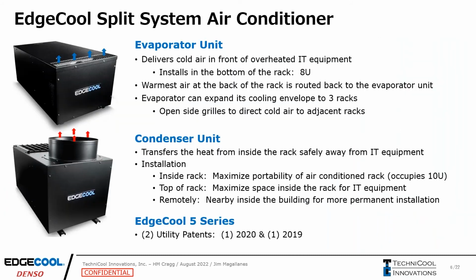So to go into a little bit more detail about our system, the evaporator, we're delivering cold air with the evaporator unit. It's always located at the bottom of the rack, and it occupies 8 U of rack space. Again, we're blowing cold air up in the front. We're capturing the warmest air in the back. That's our return for the evaporator unit. And then we can also cool down multiple racks as well. So you can see there, the primary cooling is in the front. It'll blow up right here in that rack itself. But there's also optional grills on the side here, and you can blow out cold air from the sides to cool down maybe 3 racks total.